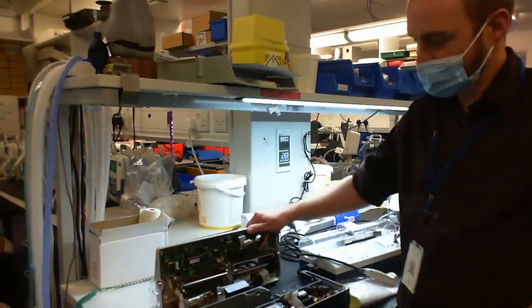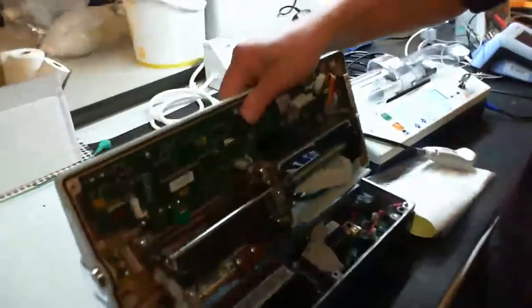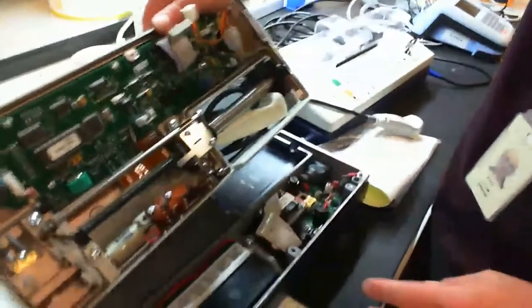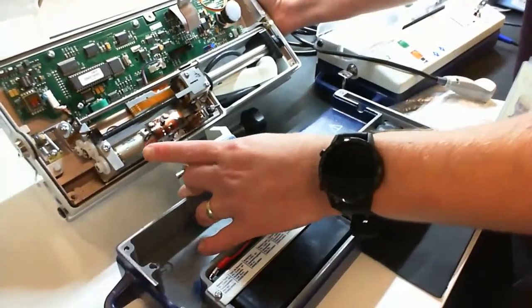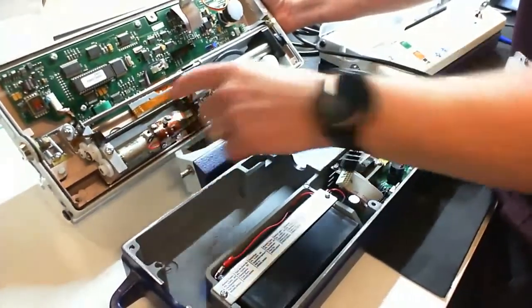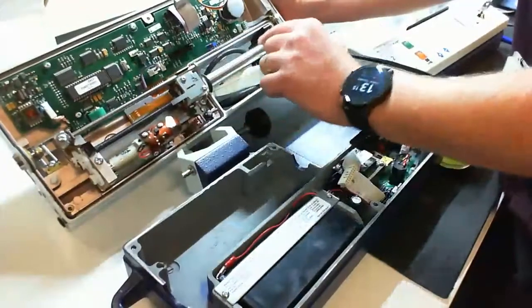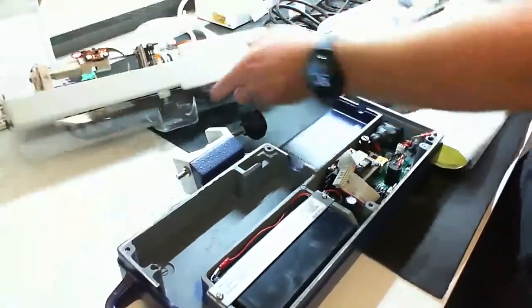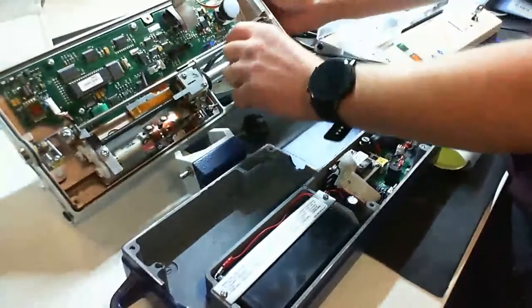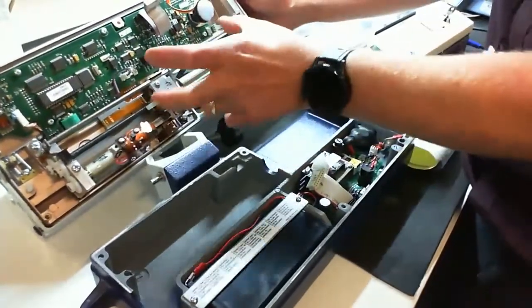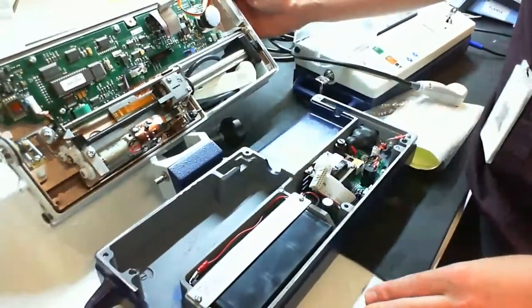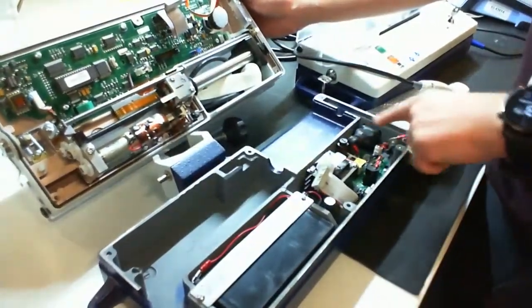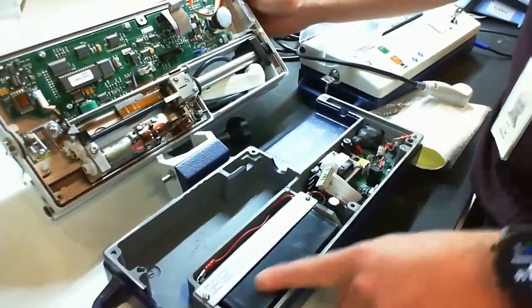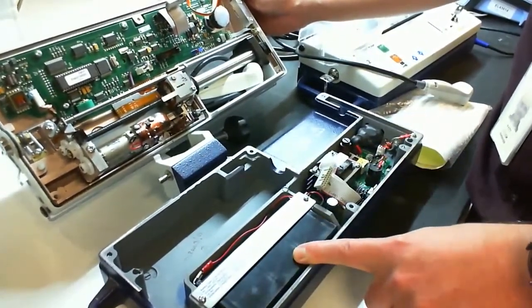If you look on the inside of this pump, the infusion pump uses an electronically controlled motor to drive a lead screw, which, when the lead screw turns, moves this plunger head, which is there. And as the plunger head moves along, it squeezes the syringe and infuses the drug to the patient. The other parts you can see are the mains power supply, and there's also a battery backup as well for if they're transferring the patient.